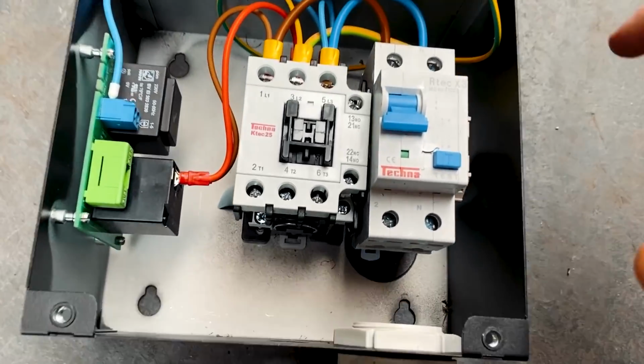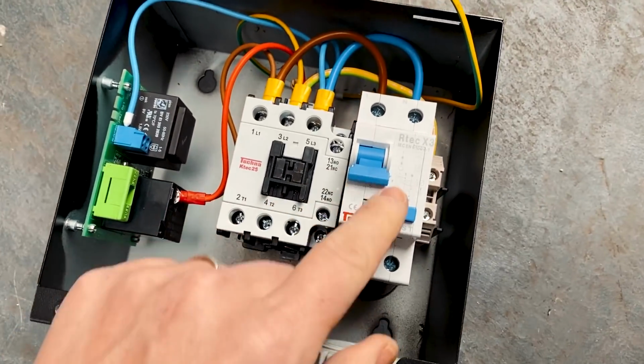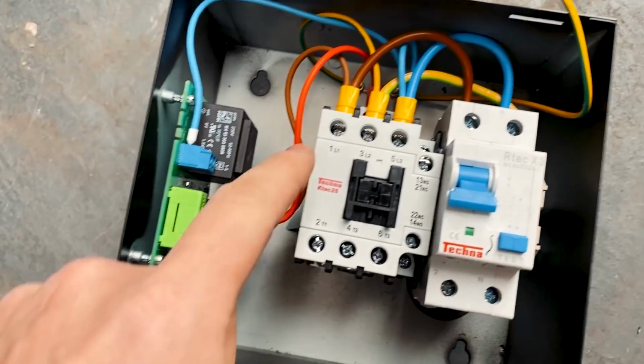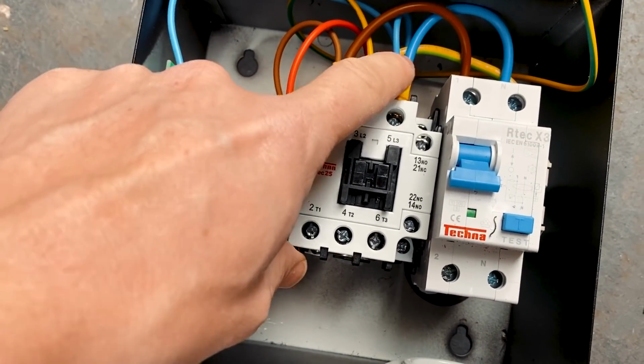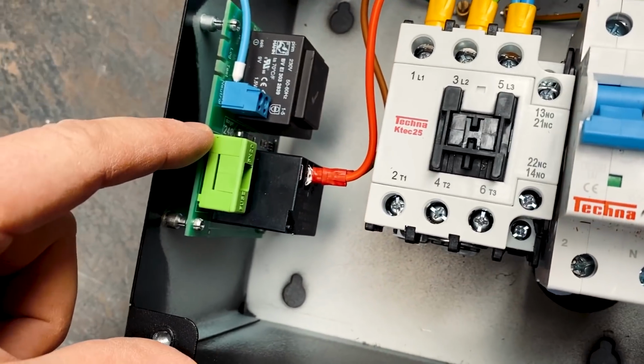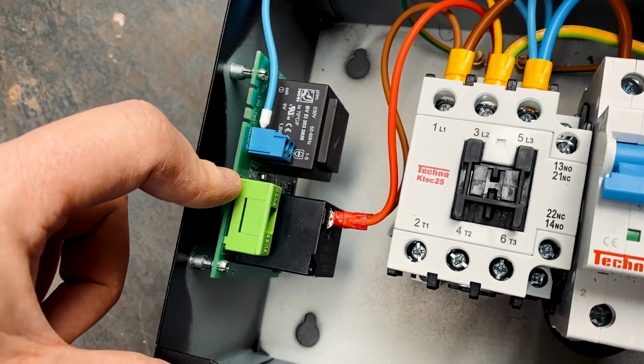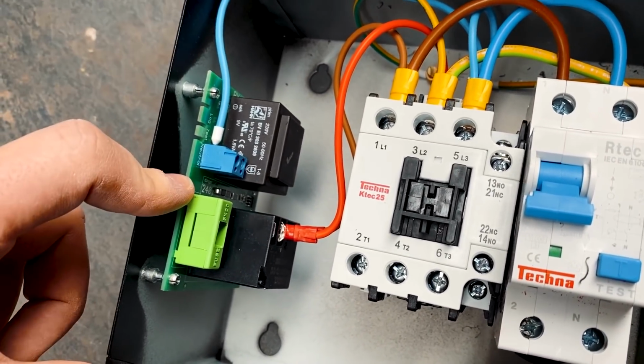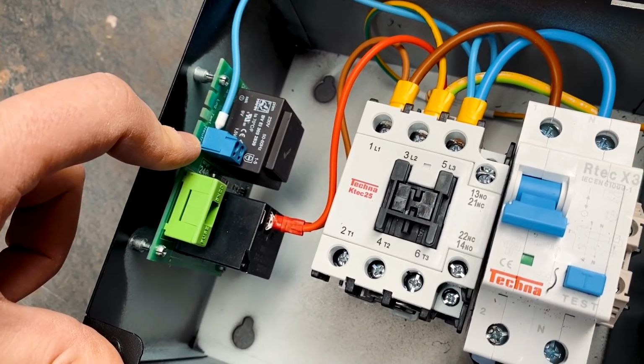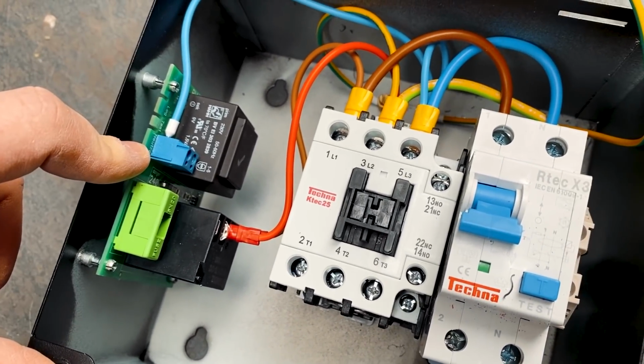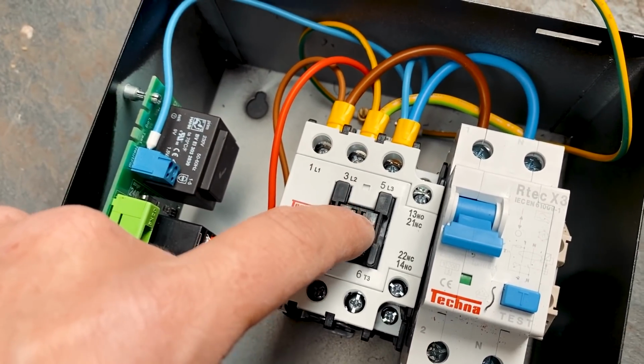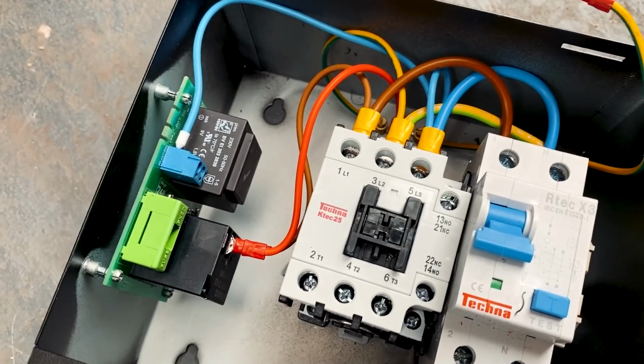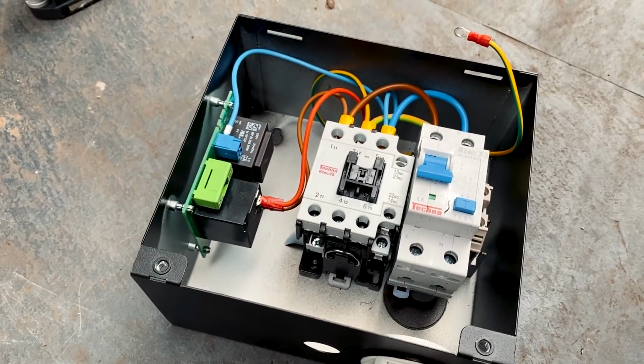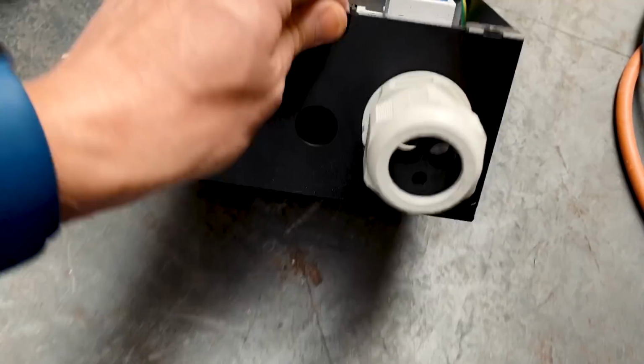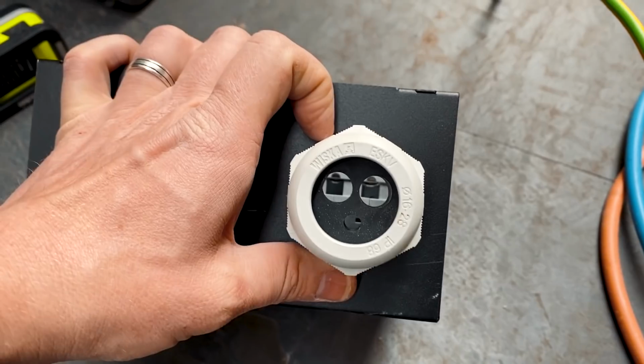So this is the inside of the MATI device. As you can see, we've got a double pole RCBO here, there's an earth terminal, and then this contactor which isolates the phase, earth and neutral conductors, and then this bit of electronic circuitry is what measures the voltage. I believe it's a voltage operated PEN fault device, so it measures the voltage, and if the voltage goes out of a certain range then it will automatically disconnect the contactor, which then cuts off the supply to all three poles.